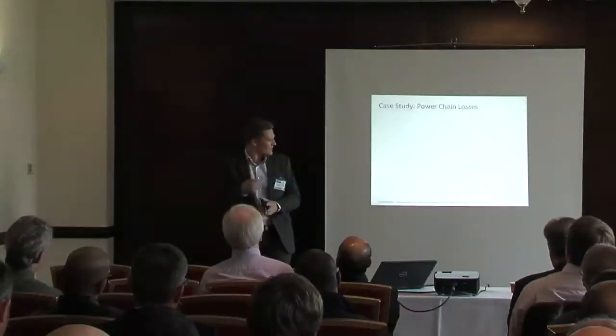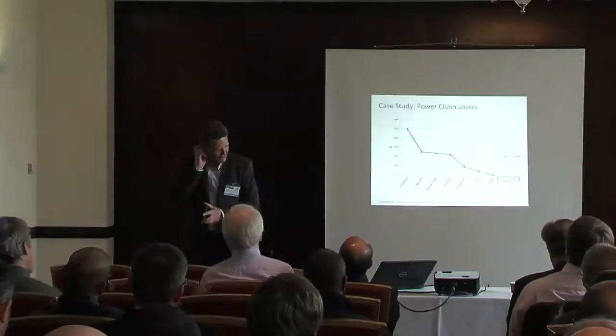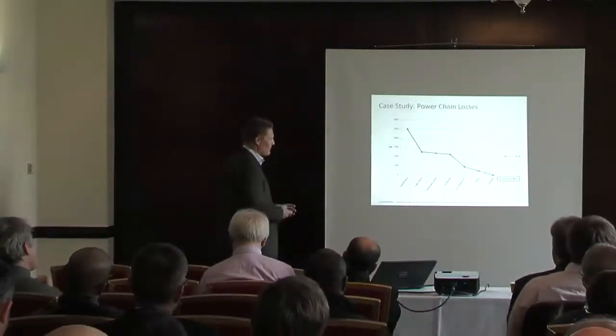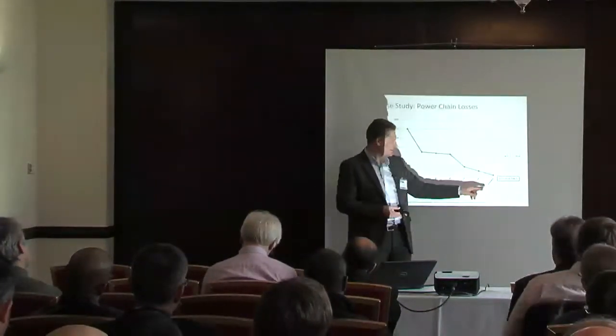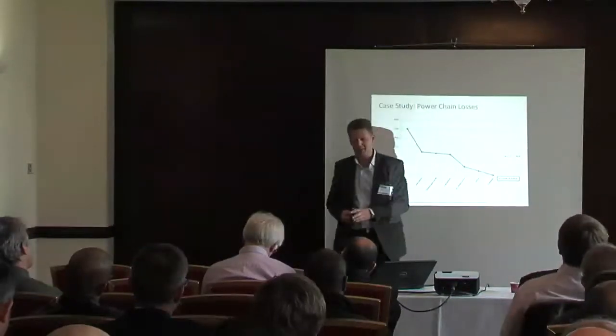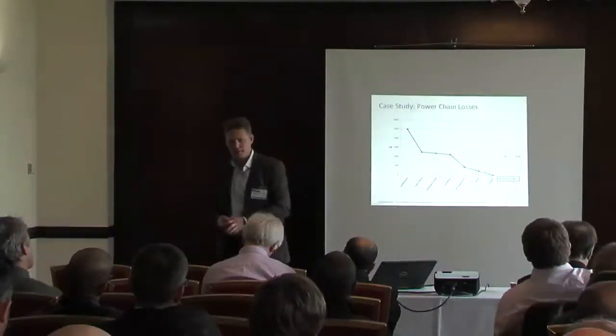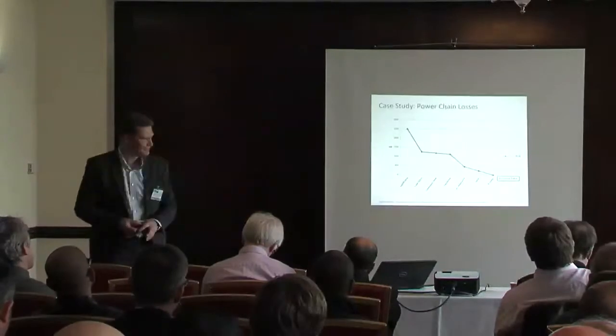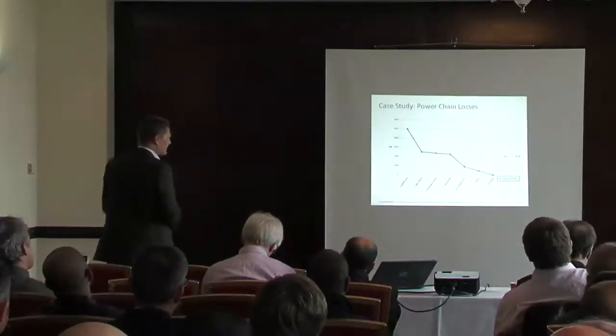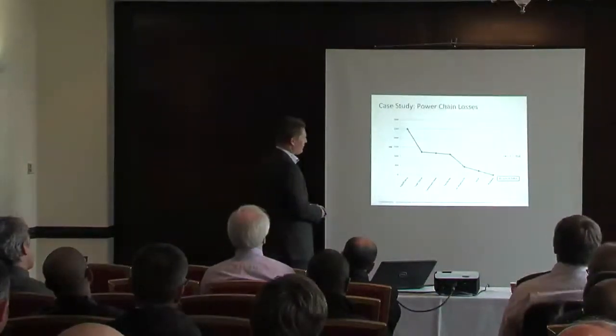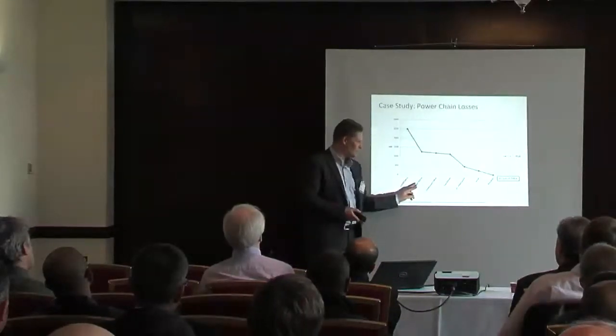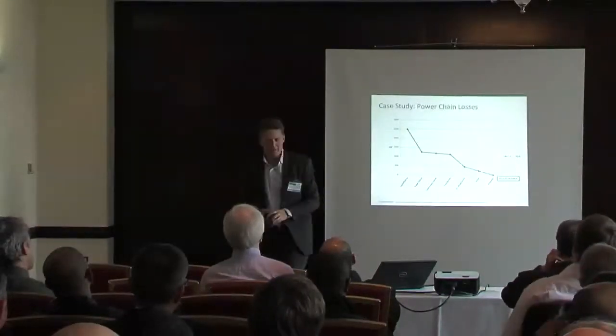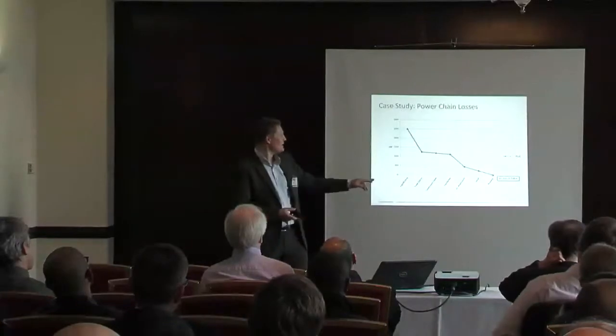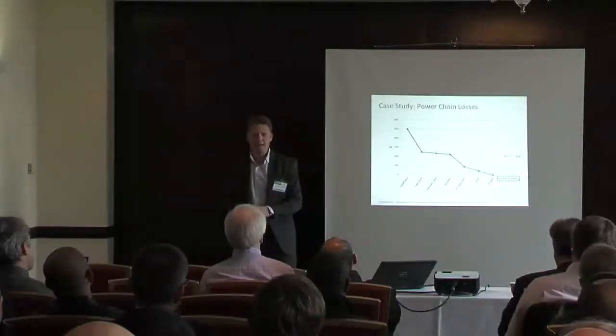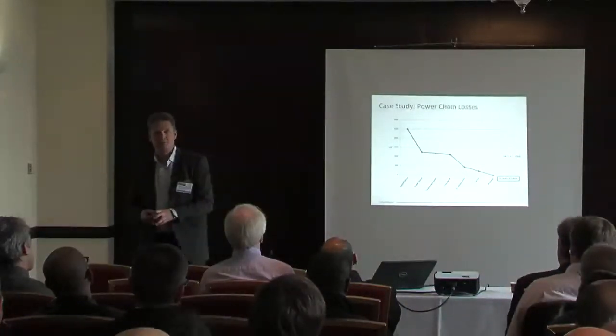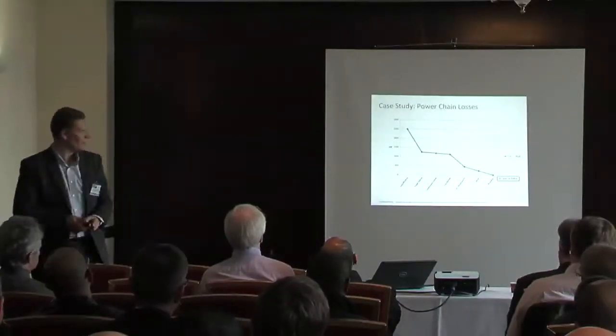Let's take another study, and this one will be a little more tricky. We'll try a backwards calculation: we have a data center, 45 racks, 10 kW, a pretty awesome data center by today's standard. To run that data center, taking all the typical losses all the way through the transmission etc., we actually need an equivalent of 2.5 megawatts just to run that data center.